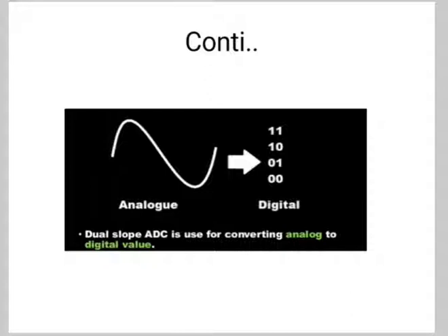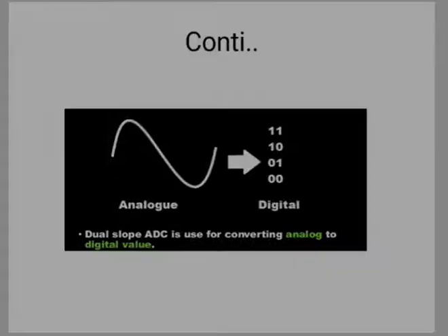One significant enhancement made to the dual slope converter is automatic zero correction. As with any analog system, amplifier offset voltage, offset current, and bias current can cause error. In addition, in a dual slope A to D converter, the leakage current of the capacitor can cause error in the integration. This effect in a dual slope A to D converter will manifest itself as a reading on the digital voltmeter when no input voltage is present.